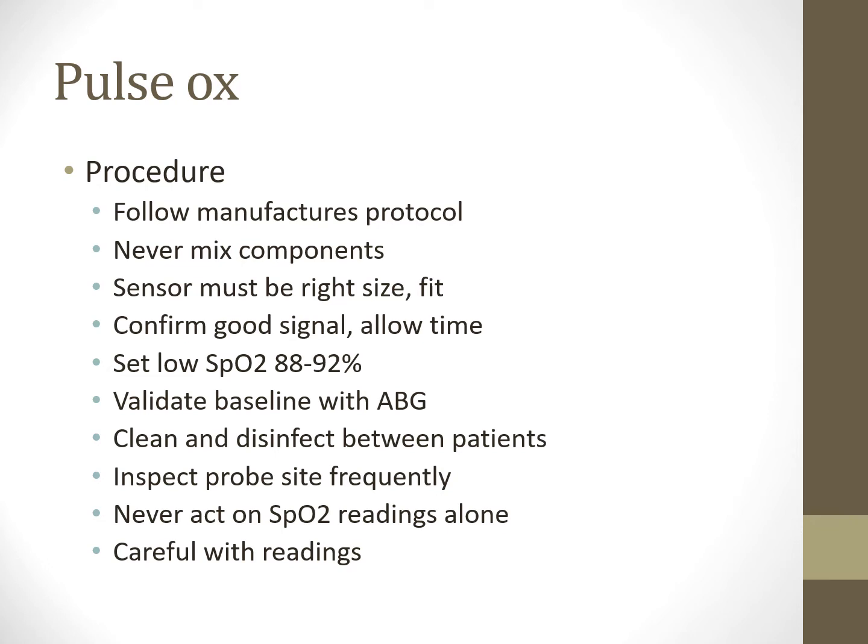But the other thing is you don't want to mix components. You don't want to put a Covidien pulse ox and a Masimo pulse ox together. And a lot of times they won't let you do that with those manufacturers. So it's just something to be aware of. That mixing components, if you are somehow able to get a signal, especially with the older machines, then that may not be the optimal way.